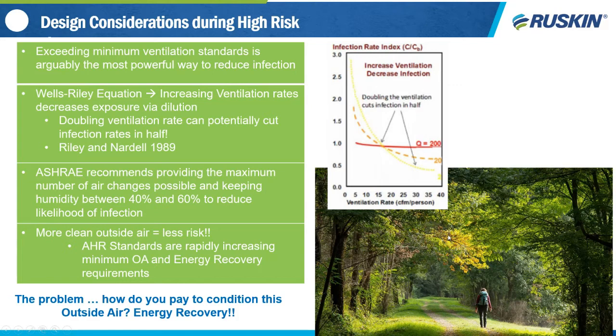Additionally, the ASHRAE handbook recommends providing the maximum number of air changes possible while also keeping your humidity between 40% and 60% to reduce the likelihood of infection. So to summarize, more clean outside air means there is less risk. There is a reason why restaurants have moved outside during these times. ASHRAE standards are rapidly increasing your minimum outside air requirements and energy recovery requirements, as we will see in this presentation. The problem is, how are you going to pay for all of this additional outside air? The answer is energy recovery.